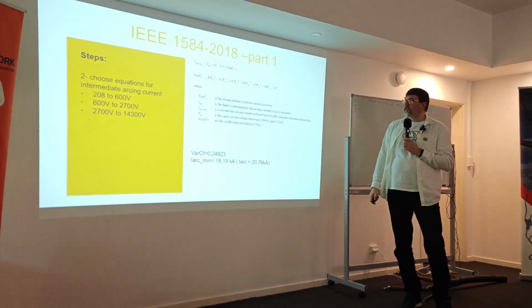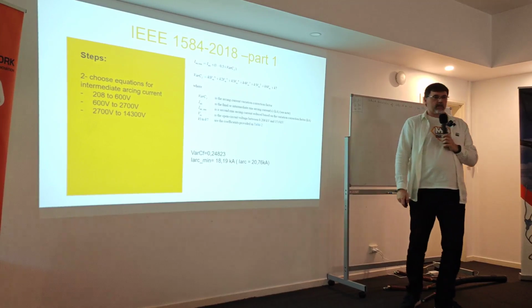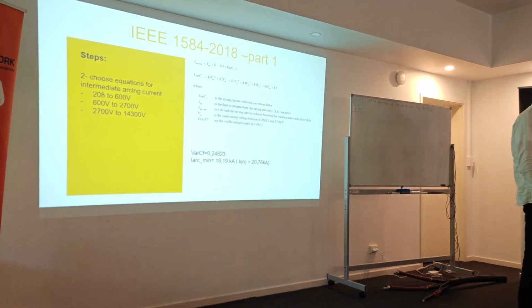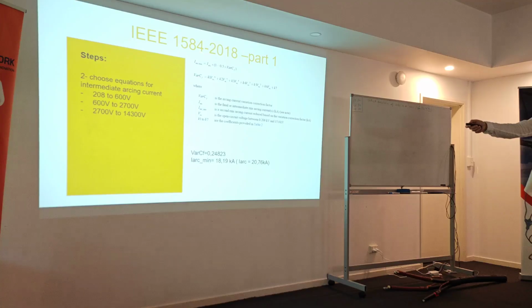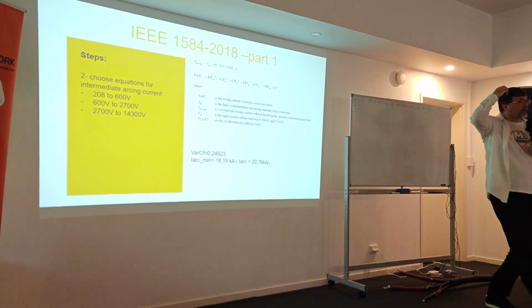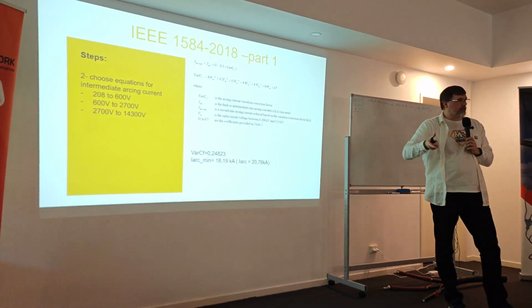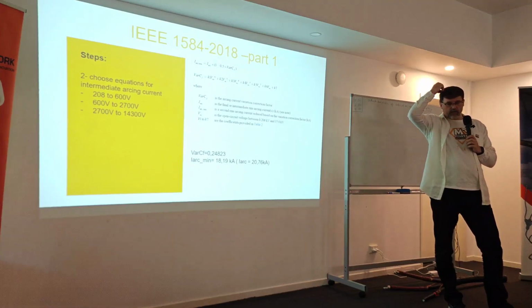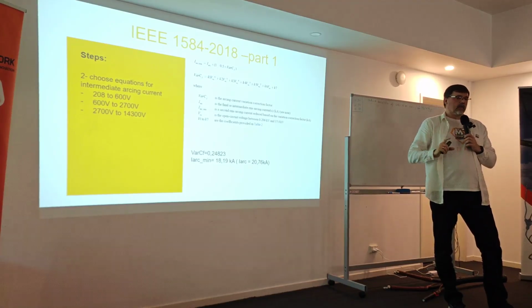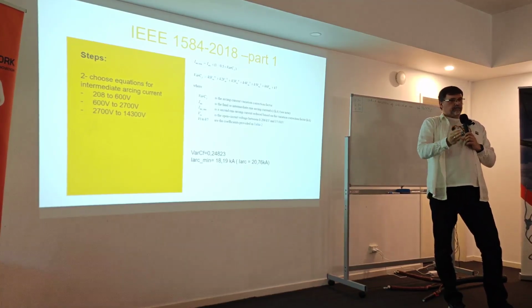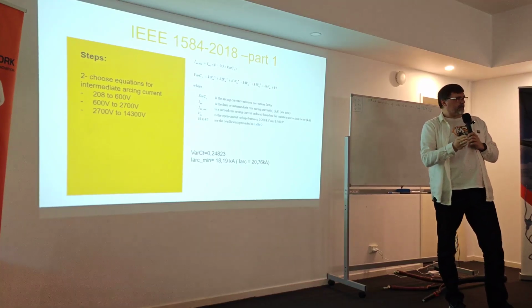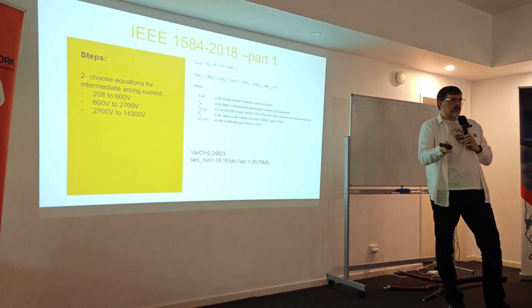Now there is something called variation factors. And this is something coming from a long time, from a practical approach, that this is I arc min, and you can see there is some factor to it from this final arc current that I calculated. The problem behind the arc is that the arc is not something that you can easily predict. And from the tests, as far as I discussed with all the guys from the IEEE, they find out that you calculate something, and it's very likely that your calculations are plus minus something, because we calculate very precisely something that we estimate, yeah?